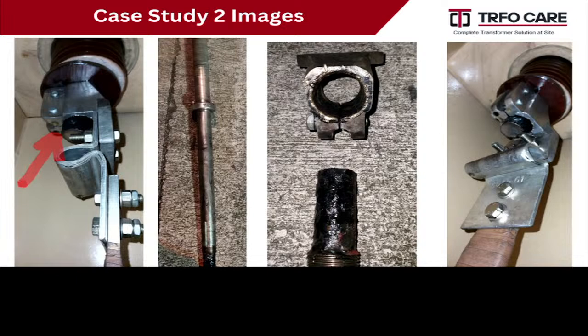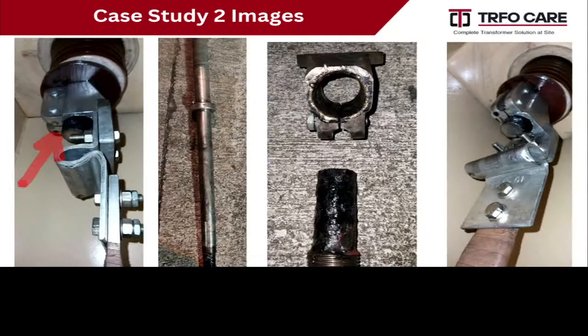Maybe at the time of erection it was found loose. So after around 6 or 8 months, because of the regular fault current going to the neutral bushing, this connector burnt and we replaced it with a new one. See that rod is completely burnt, that palm type connector is completely burnt.